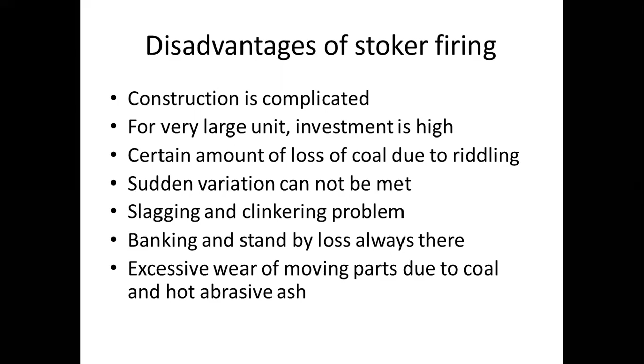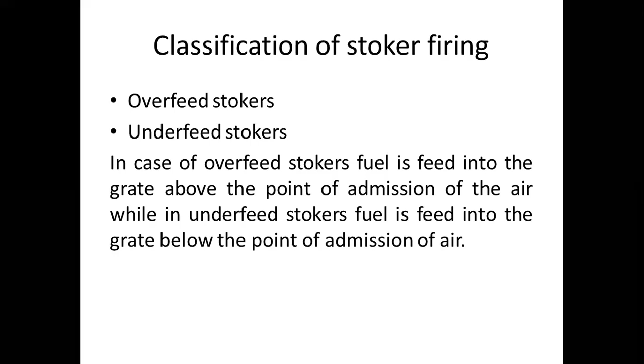Now, if I am talking about the classification of stoker firing, see, all the stoker firing can be divided into two parts: overfeed stoker and underfeed stoker. See, whenever we are saying overfeed or underfeed, it tells us the relative position of the fuel admission over the air. Means this is the relative position of the admission of the fuel with respect to air. In case of overfeed stoker, fuel is fed into the grate above the point of admission of air. While in underfeed stokers, fuel or you can say coal is admitted in the furnace below the point of air admission. इससे आप लोग ध्यान रखें.